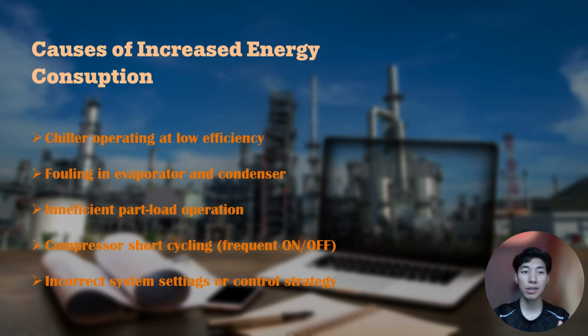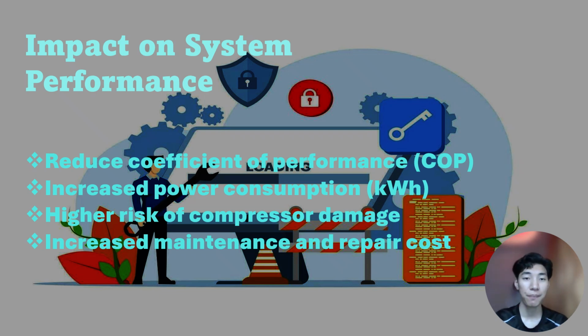Okay, so we go to the causes of increased energy consumption. The chiller operating at low efficiency, then fouling in the evaporator and condenser, inefficient part load operation, compressor short cycling on and off, and lastly, incorrect system settings or control strategy. Okay, next we go to the effects on system performance. First, reduced coefficient of performance. Next, increased power consumption. And next, higher risk of compressor damage. And lastly, increased maintenance and repair costs.